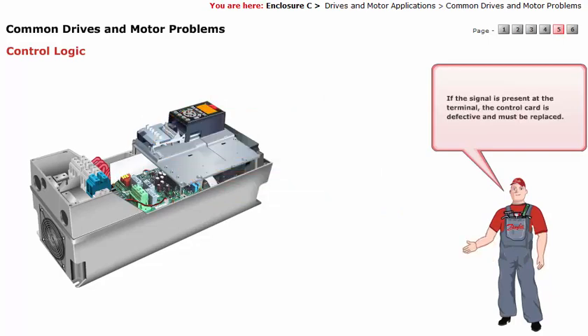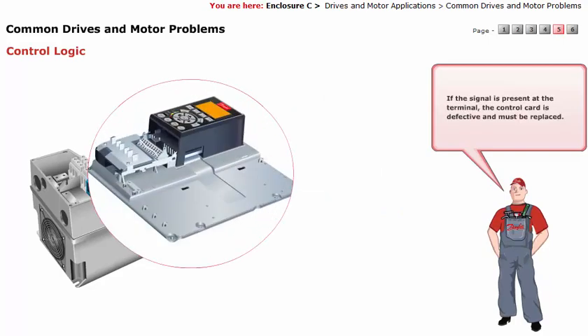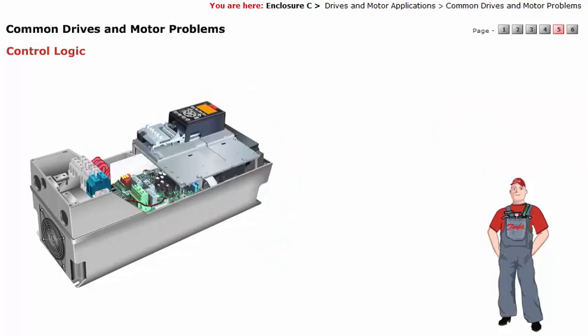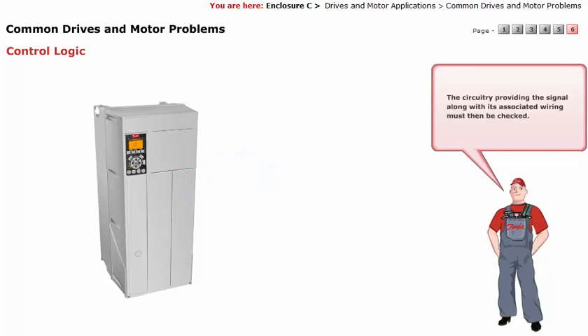The presence of a correct reading indicates that the desired signal is detected by the microprocessor of the drive. If the signal is present at the terminal but there is no correct indication, the control card is defective and must be replaced. If the signal is not present, the problem is external to the drive, and the circuitry providing the signal, along with its associated wiring, must then be checked.